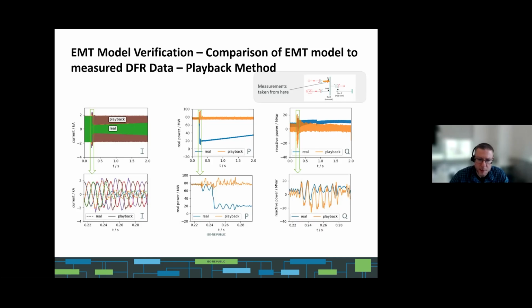That was very unexpected, because when we go back to the models and play back the same voltage and angle into the models, we didn't see that performance. Even though it got all the way through the interconnection studies and our vetting, because this was not a sort of contingency or disturbance we normally would look at, the model did not respond in the way it actually did in the field.